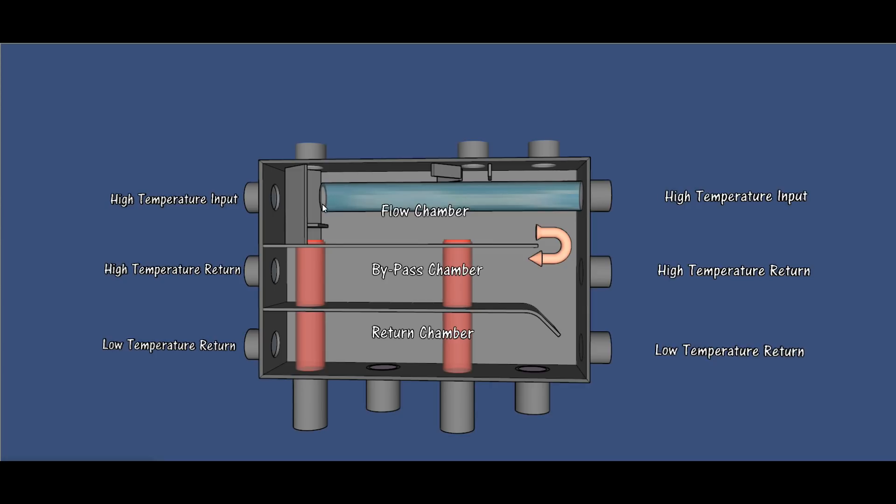If water flows in from a boiler, say from the left port or from the right, traveling through a pipe that passes through the unit, they both meet this baffle, turn back, and then flow from left to right. This arrow represents a 100% open bypass, so there's very little resistance inside the unit.